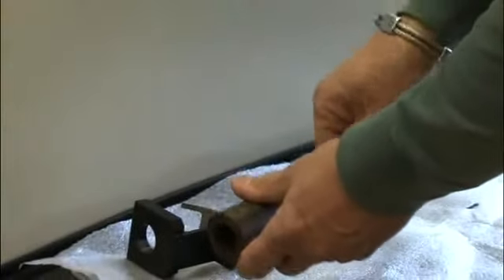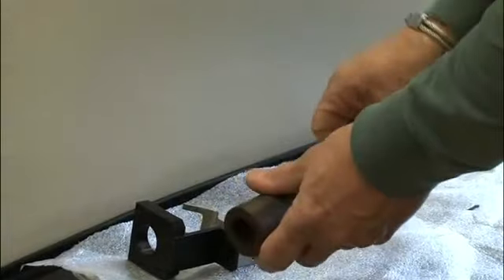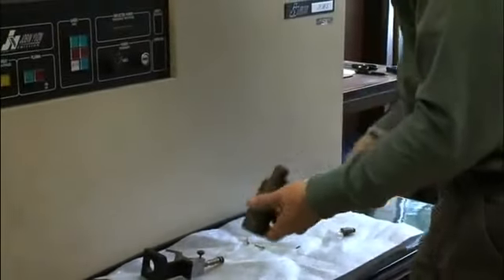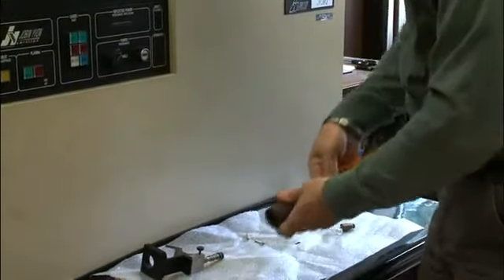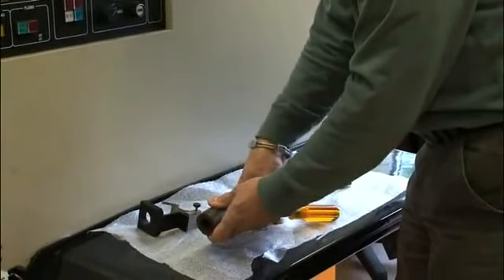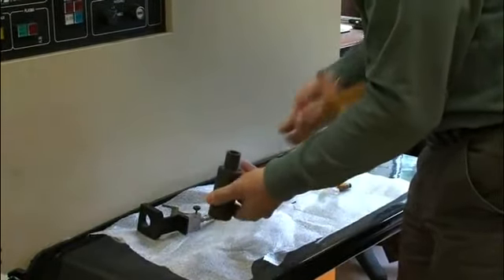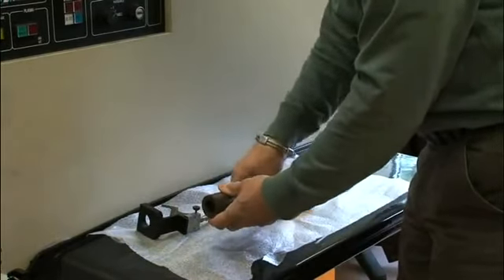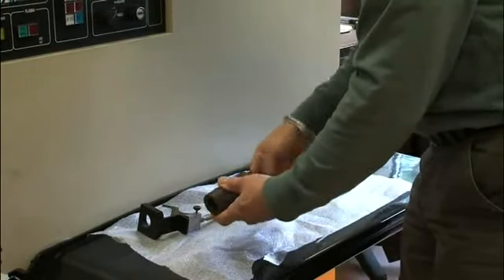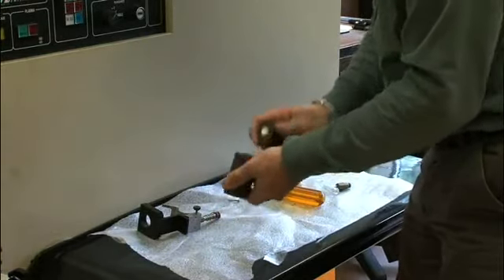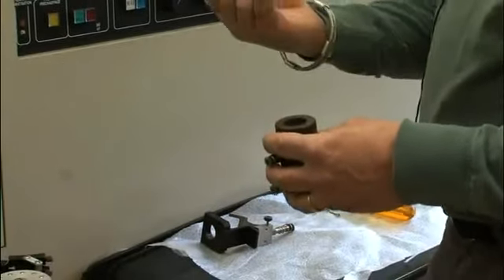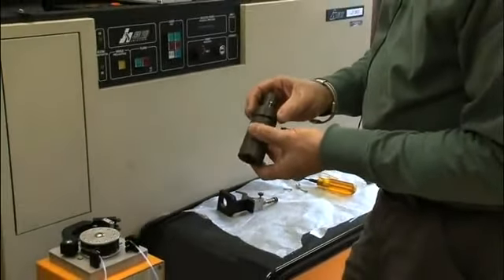The torch has 7 O-rings, 2 for each one of these tubes, 2 for this guy, and 1 for the bottom of the injector. And then there's another one right in here that separates the 2 halves. This doesn't come apart. So you basically have 4 O-rings through here, which a dental pick is good to have to pluck them out because they're hard to get back in and pull out sometimes.